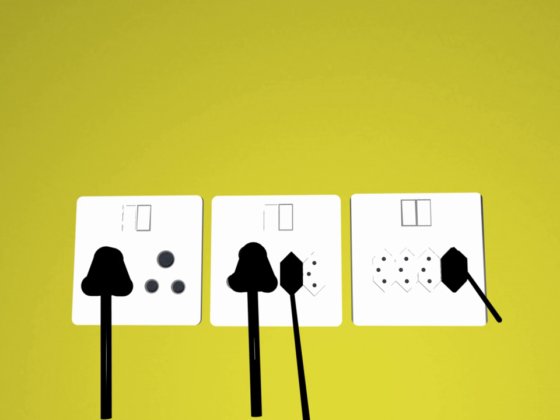The IEC 60906-1 plugs are also rated for up to 16 Amperes, while the BS-1363 plugs are rated for 13 Amperes. The unfused IEC 60906-1 is incompatible with UK law which requires an appropriately rated fuse in the plug to protect the attached flexible cord.